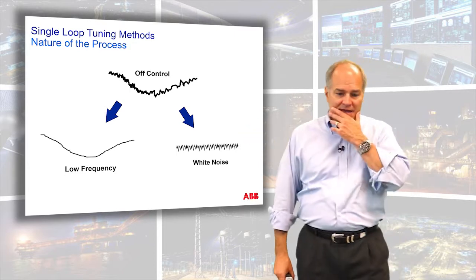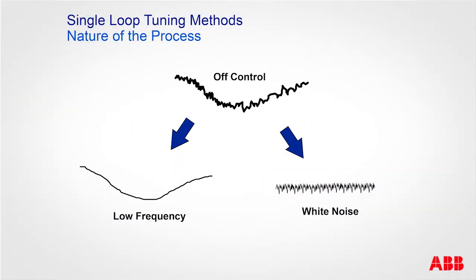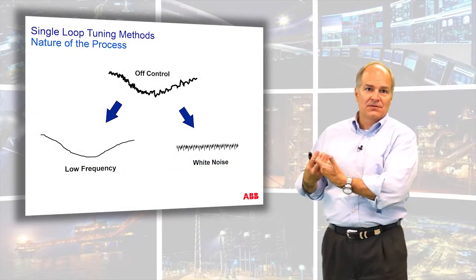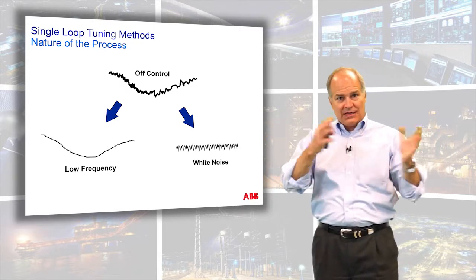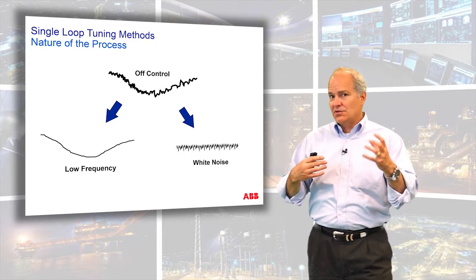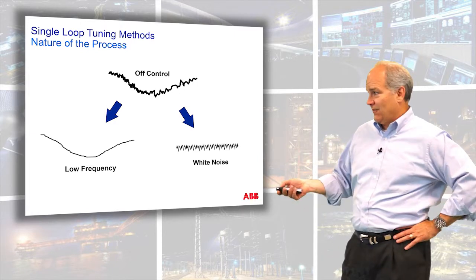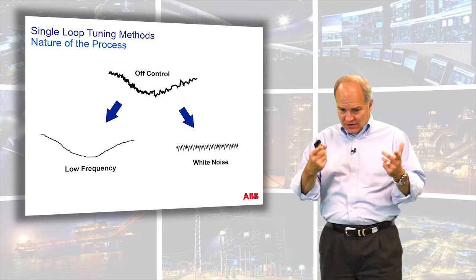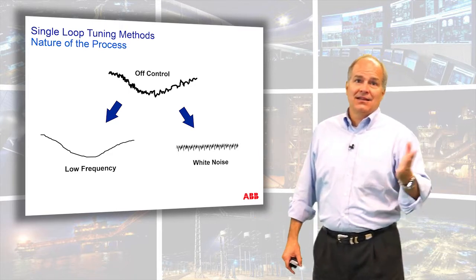Now let's step back and look at a signal that just ebbs and flows. Can you deconstruct it in your mind? If this is my signal off control and I were to remove the noise, here's the noise and here's the low frequency component. If you add those back together, you can get the total signal. By deconstructing the signal into low frequency and noise components, we get closer to identifying what control can deal with. Control is designed to fix the low frequency — not the noise.